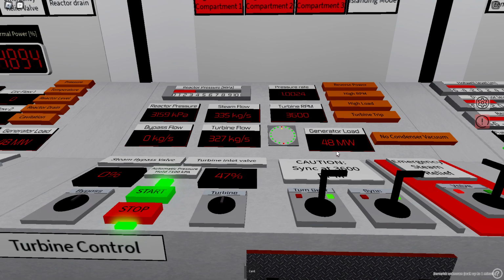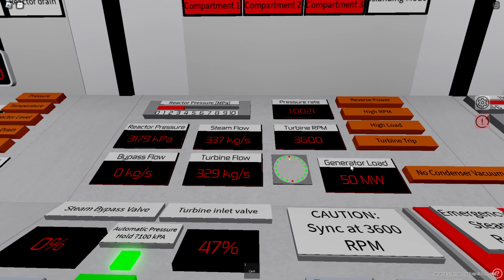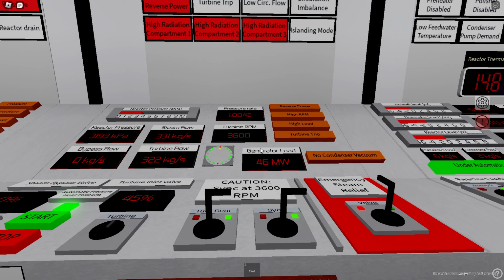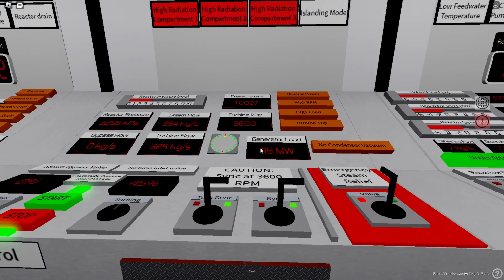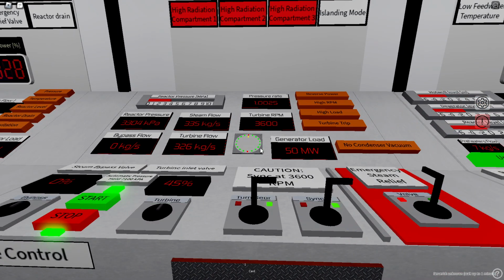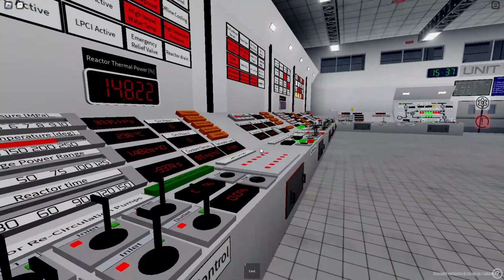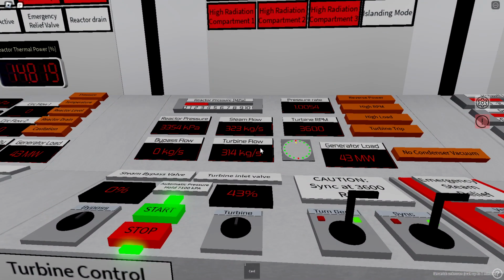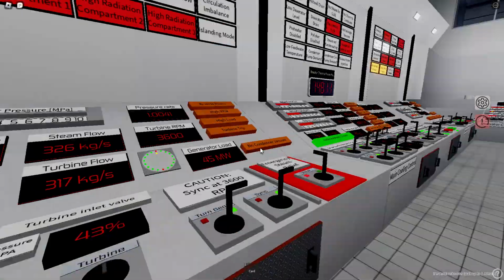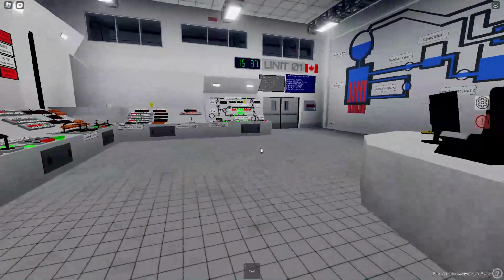You want to keep your generator load above 0 megawatts. If it goes below 0 megawatts, like -3 megawatts, it means that you're using more power to keep the generator synced to the grid than what you're actually making. And this will cause reverse power, which will desync the turbine from the grid, and then you're slightly in trouble. Because if you're new and you wouldn't know what to do, everything will just shut down basically.